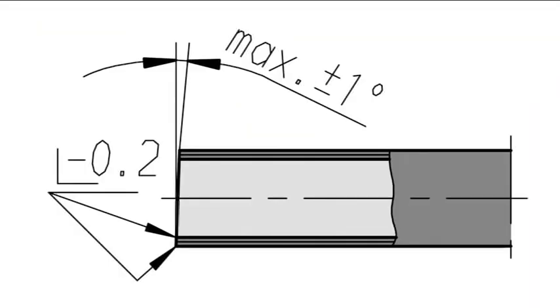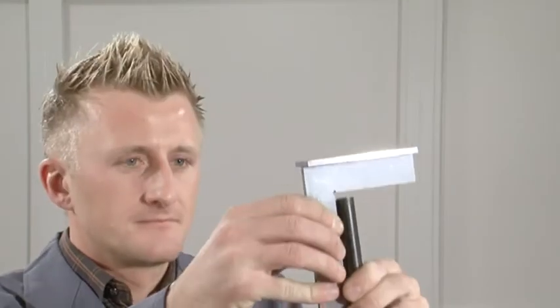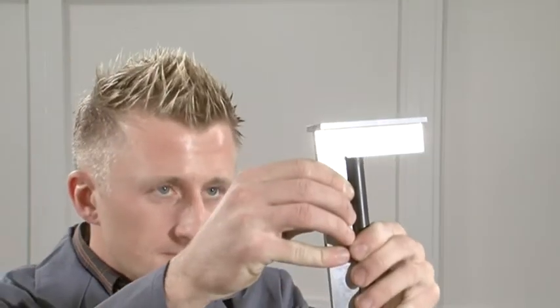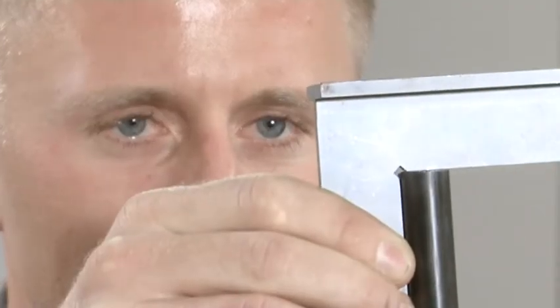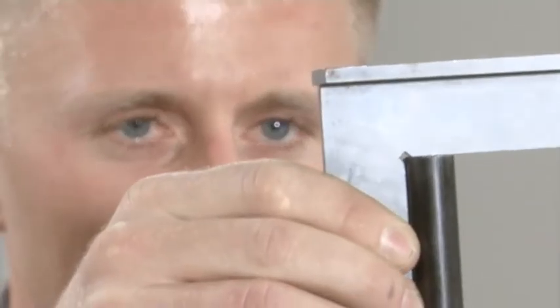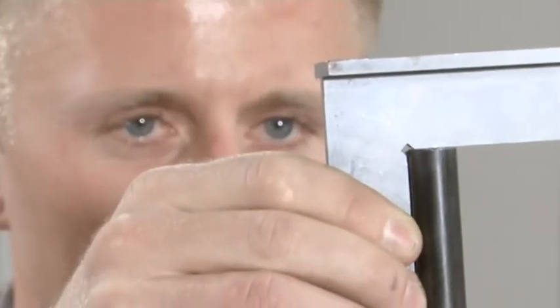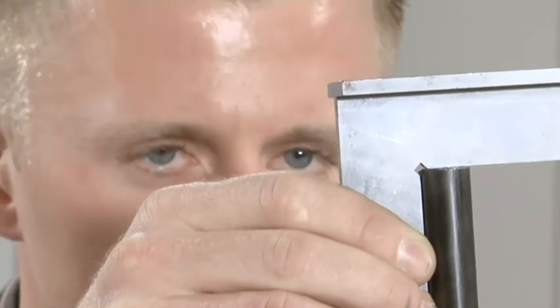An angle tolerance of plus minus one degree is permissible. Remember that slanted saw cuts or wrongly burred tubes reduce the life duration and sealing properties of the connection.